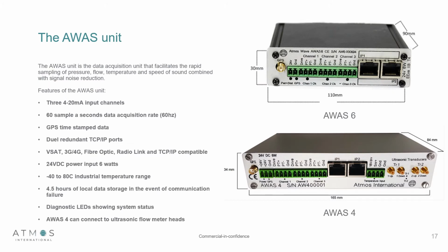So how do we get such accurate leak location? How are we so sensitive when we're utilizing Atmos Waveflow? Well, we do this by combining software with our own hardware, and we utilize a unit called the AWAS unit. And this is a very simple data acquisition unit that allows us to sample data at a high rate, around 60 samples a second. We can take 4 to 20 inputs from flow meters, pressure transmitters, and temperature sensors. Then that analog signal is digitalized, sent to servers or a cloud, and then the data analysis is performed within our software. There is no filtering or anything applied in these AWAS units. It's purely digitalized into a digital file and sent to our software, where then we can do the analysis we require.